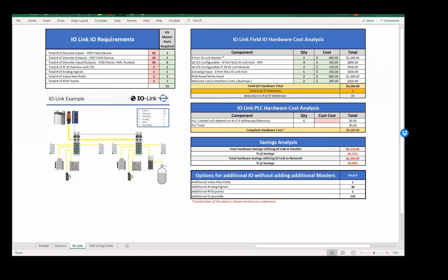Absolutely. So just for fun, as you can see, we used 11 IO-Link master ports. We used two masters, mm-hmm, for a total of 16 ports. That gave us 5 additional IO-Link ports that are not being used. Mm-hmm. So in the field, or a customer comes to you and says they want to add more IO, more traceability, really kind of a minimal issue, because you can see, at least in our application here, if we wanted to, without buying additional masters, adding IP addresses or anything on our system, we could add 5 additional valve manifolds, up to 40 analog signals, 5 RFID points, or 150 additional IO points. And again, that's just with buying a simple configurable IO block or an IO-Link COM module for a valve manifold, but not having to add more network devices, more IP addresses.